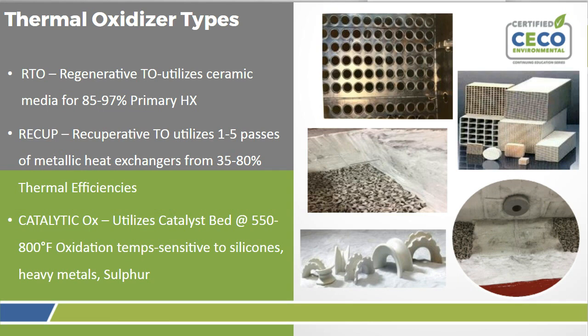A catalytic oxidizer typically will use a catalyst bed, and that's going to be about 550 degrees Fahrenheit to 800 degrees. And those are sensitive to silicones, heavy metals, sulfur compounds. If you have those in a stream, probably not a good application. So know your application, know what's in there with your solvent inventories and so forth.